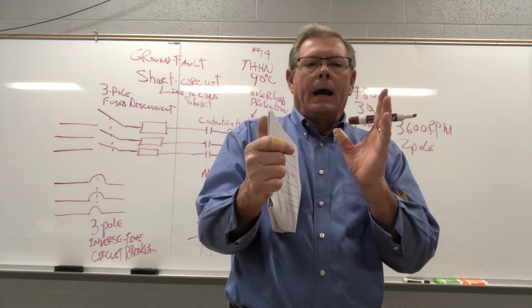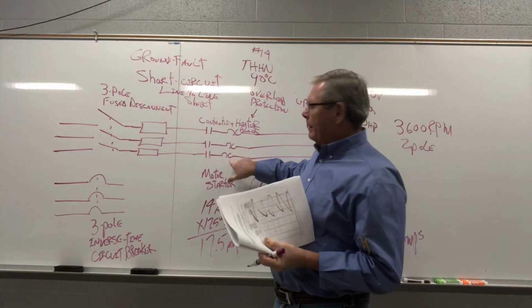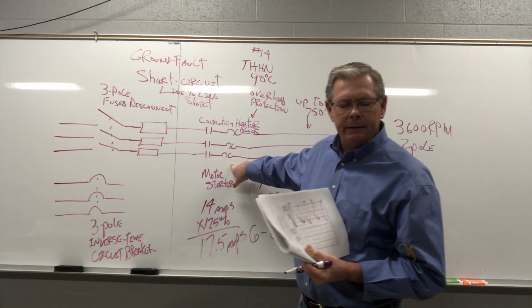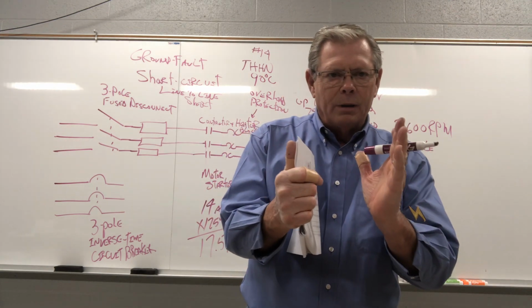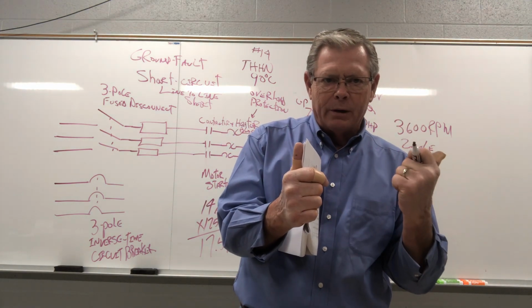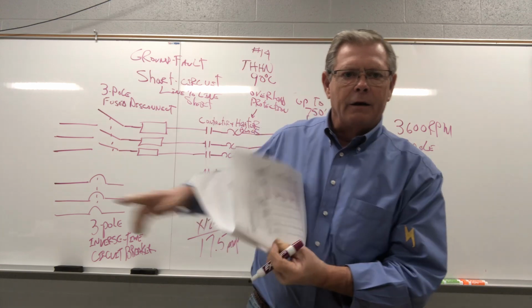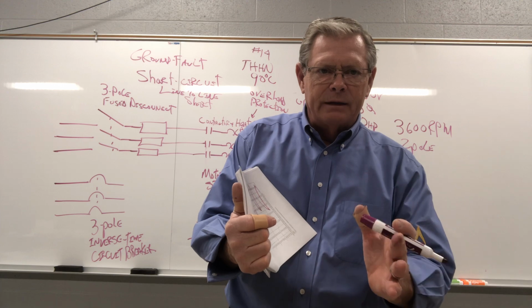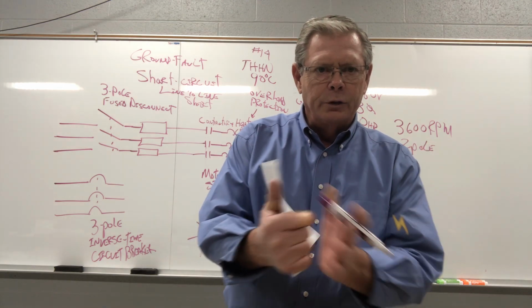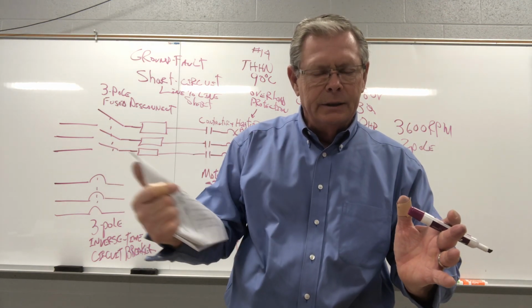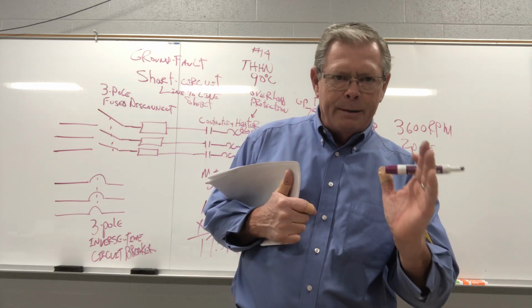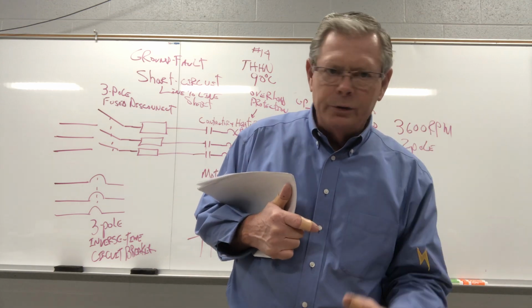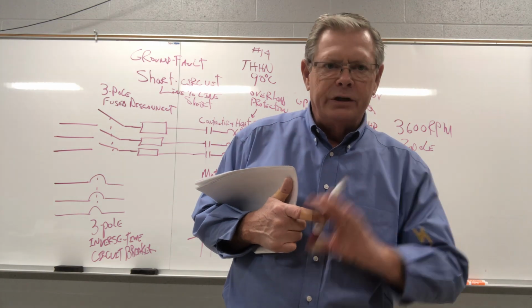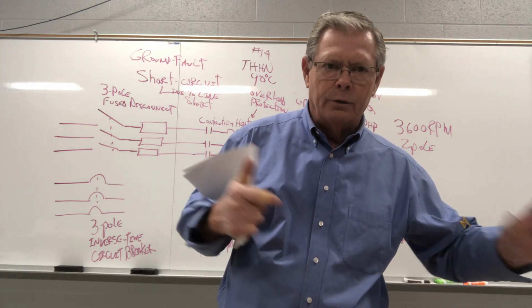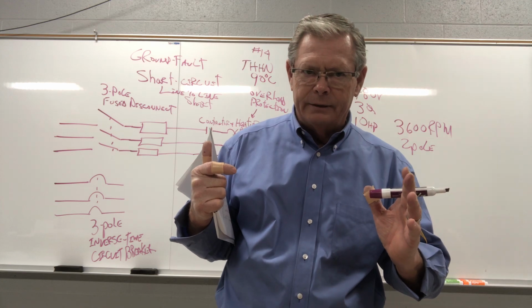okay? And here's the reason for that. You remember when we were talking about the overload block? We have a separate overload block that protects that wire from burning up from overload. Then our fuses and our breaker take care of line-to-line short and a ground fault. So they're separated in a motor circuit. But at home, that 15 amp breaker that feeds your living room has to do it all, okay? So it's a different way of calculating. So we always need to remember that, okay?